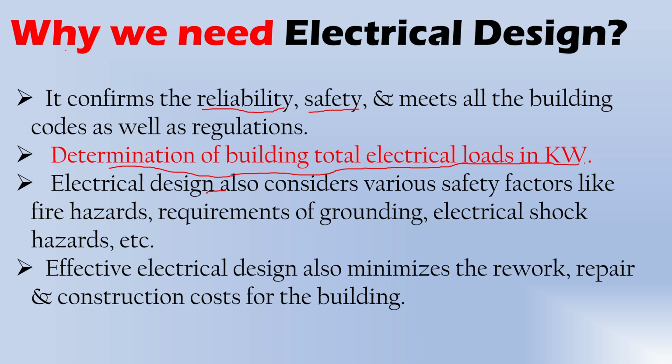Based on this load, you go for the transformer, then the LV panel, then the submain, and based on that we select all the cables. Your whole project revolves around the total connected load, so you determine the total electrical load in your electrical design. That's the main reason we need electrical design.